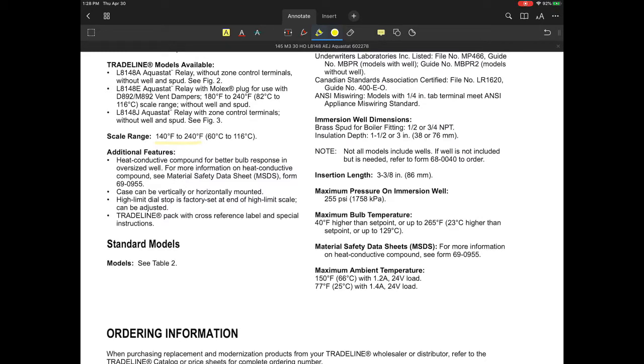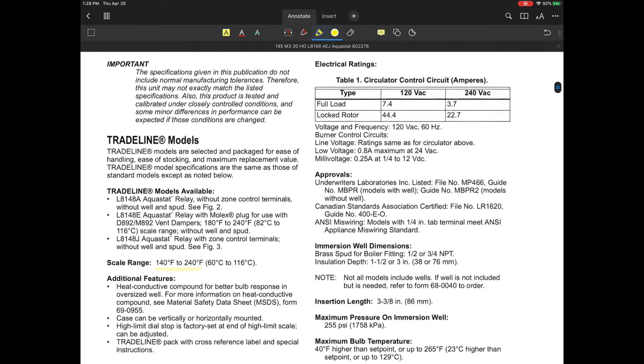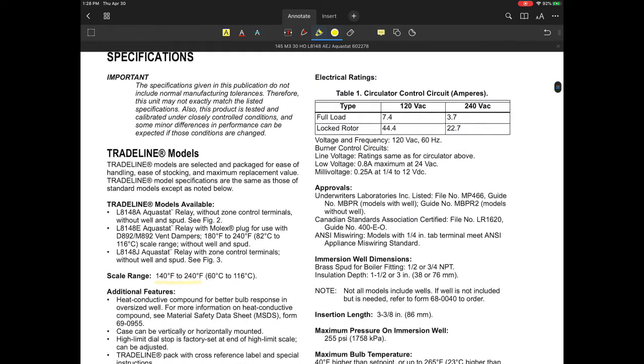What you probably will recognize or remember is that the approximate temperature where natural gas, propane or oil will condense is in the vicinity of around 130 degrees, typically 125, 130-ish. So what that means is if you're going to maintain 140 in your boiler, you're going to keep that boiler out of what I would call a condensing situation, and that's something you have to be aware of. So that's a big one on there. Let's take a look at some of the other details.